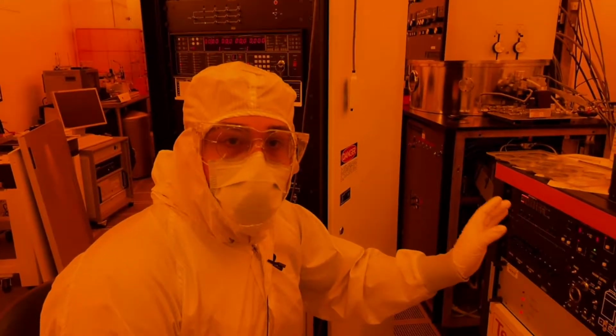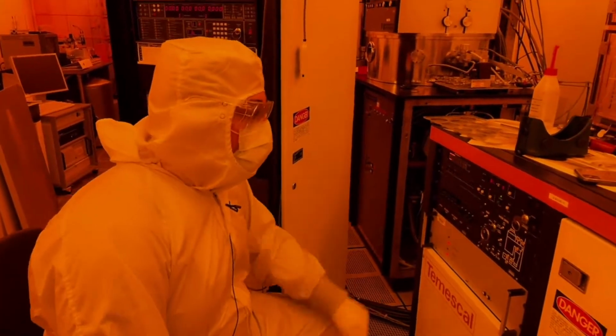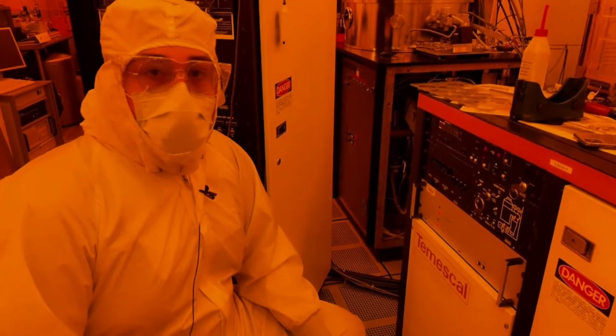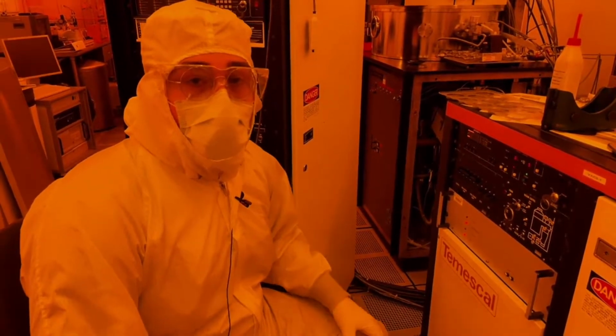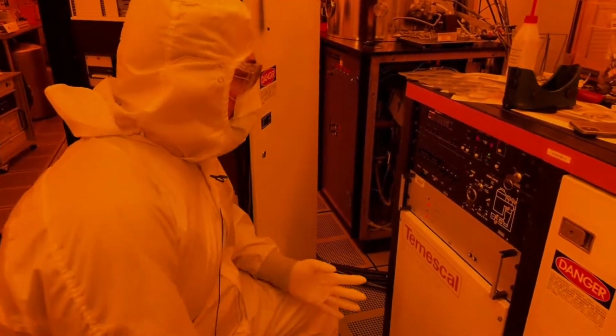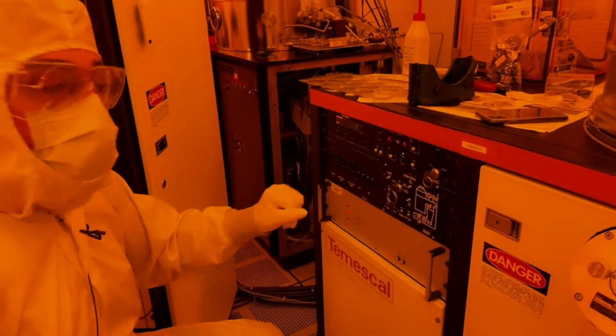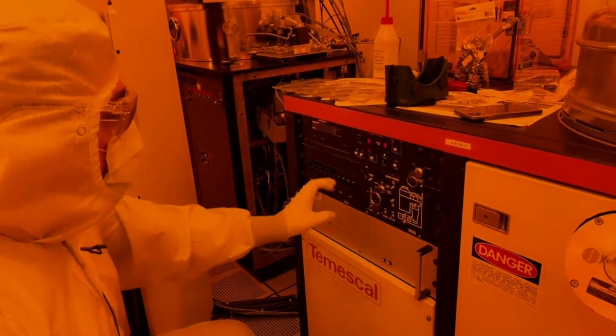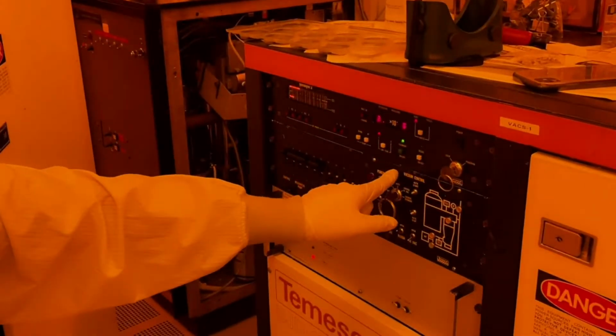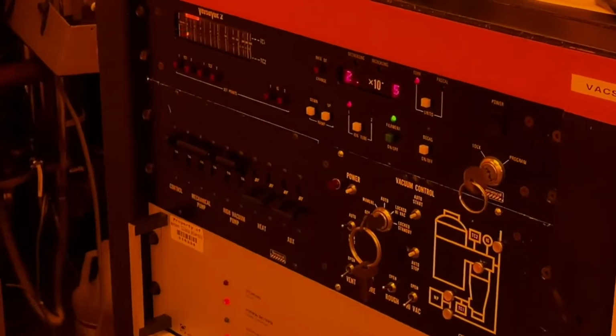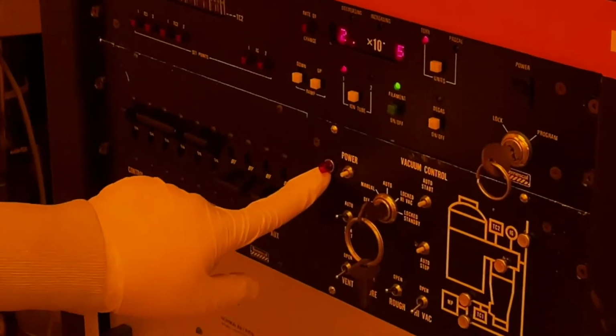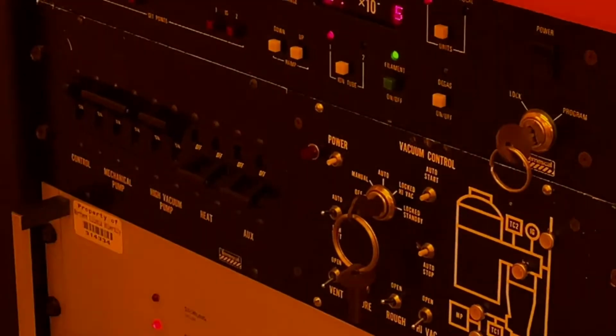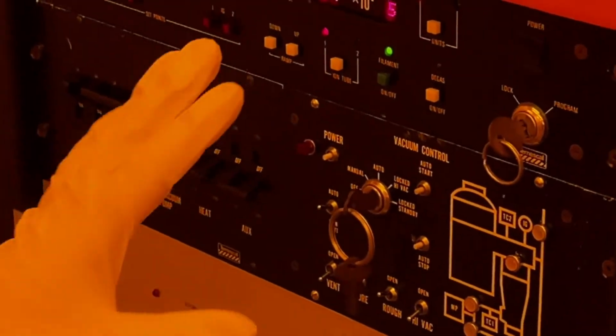Okay. So while we wait for the chamber to get to a proper vacuum for deposition, I'm going to go over some troubleshooting stuff. Most common is going to be problems associated with power outages in the building. When the power goes out, a lot of these circuits get knocked out as well. For example, almost always if the power goes out, this main vacuum control panel is going to turn off. You won't be able to tell because the power LED indicator is burnt out. But when you come in, it won't be running.